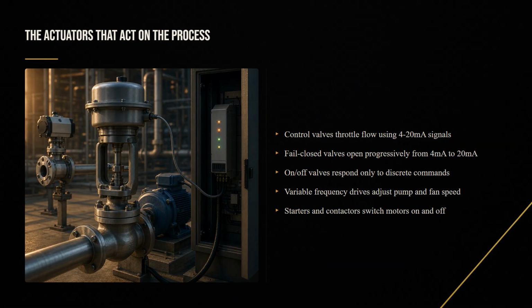Control valves throttle flow on a 4 to 20 milliamp input signal. In fail-closed valves, the most common configuration, 4 milliamps is fully closed and 20 milliamps is fully open. 12 milliamps positions the valve at 50%. On-off valves operate on a discrete signal, a simple on or off command, no middle values. Variable frequency drives control motor speed by varying the electrical frequency to the motor. Slower frequency means slower pump or fan. Motor starters and contactors start and stop motors on discrete commands. These are the physical outputs of every control loop, the feedback cycle you saw in Lecture 2.4.